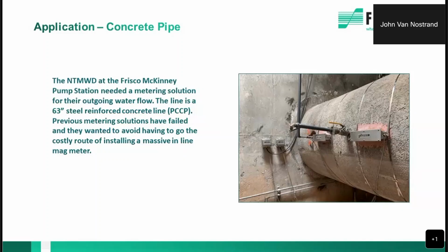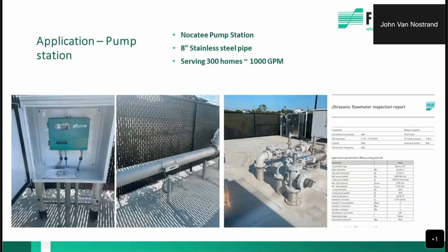We said, look, let's give it a try. We went out there, we installed the meter, and essentially what we did here is we used a Bondo filler like you would buy from an auto parts store, and smoothed the pipe and installed our transducers, and we got accurate flow measurements before lunch. So our technicians were in and out of this location by lunchtime, and the customer is extremely happy. In fact, there are other utilities that use concrete pipes that have been to that site and visited, and as a result have placed orders for meters on their systems.